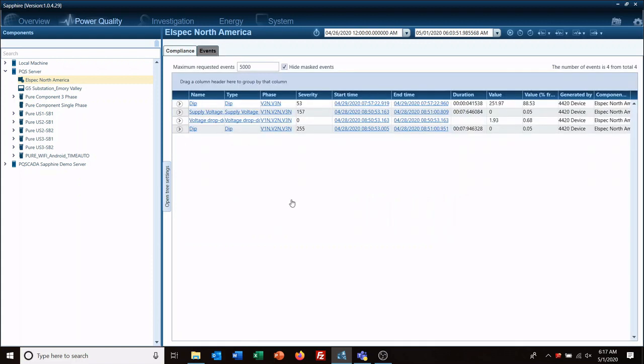Okay, so now the events is what you would expect to see in a typical power quality monitor. You would go out and you would set your trigger events for certain levels. You'd bring it back and you'd look at your events. We do do that, but the great advantage to our continuous waveform recording versus a standard PQ meter is if the data is not here, you can go back over to your systems tab, go to your events tab.